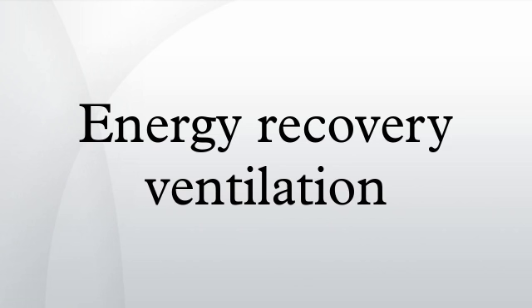Methods of the transfer: an energy recovery ventilator is a type of air-to-air heat exchanger that not only transfers sensible heat but also latent heat. Because both temperature and moisture are transferred, ERVs can be considered total enthalpic devices. On the other hand, a heat recovery ventilator can only transfer sensible heat. HRVs can be considered sensible-only devices because they only exchange sensible heat. In other words, whereas all ERVs are HRVs, not all HRVs are ERVs, but many people use the terms HRV, AAHX, and ERV interchangeably.